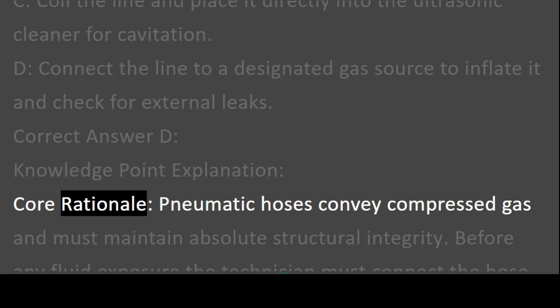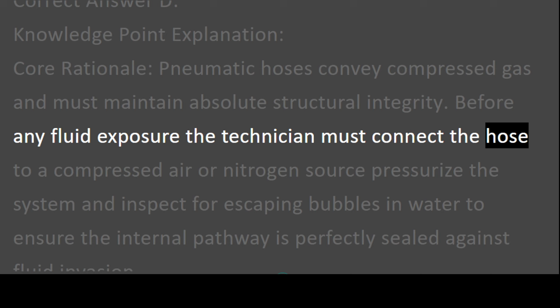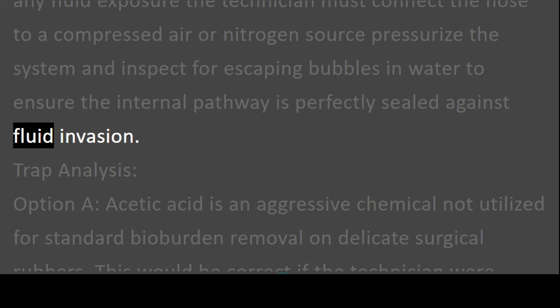Correct answer D. Knowledge point explanation. Core rationale. Pneumatic hoses convey compressed gas and must maintain absolute structural integrity. Before any fluid exposure, the technician must connect the hose to a compressed air or nitrogen source, pressurize the system, and inspect for escaping bubbles in water to ensure the internal pathway is perfectly sealed against fluid invasion.